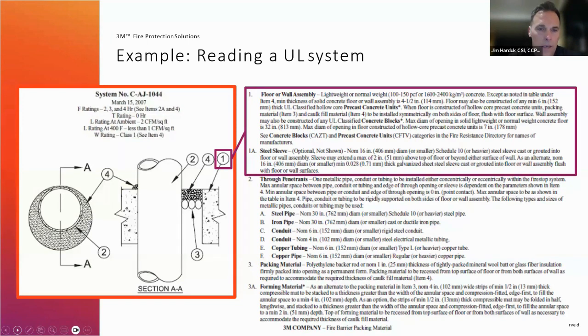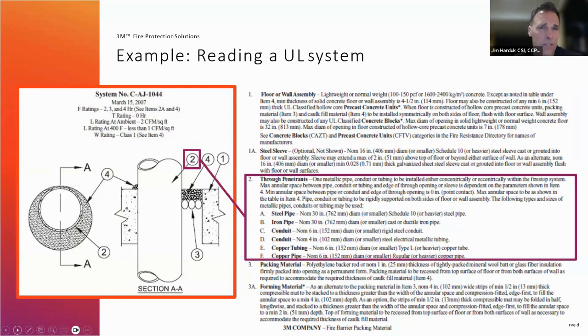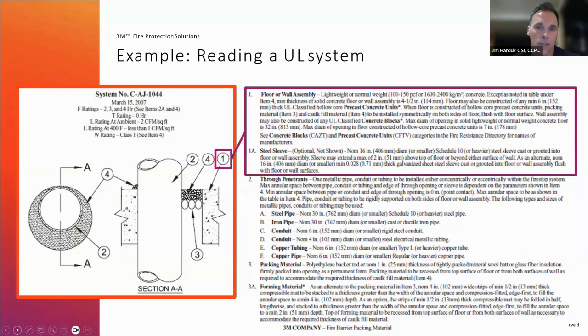And then in a system drawing, you have those items that I've just identified, and then you always have a small detail, and it'll show what the penetrating item is. It'll have a brief cutaway section of the floor or wall assembly, and it'll show a little bit about the fire stopping materials that are used. But they're always laid out the same way. So at the beginning of the system drawing, you have the identification of the assembly. It'll tell you if it's a floor or wall assembly. It'll tell you how it's constructed, what the thickness is. Sometimes sleeves are optional, sometimes they're required, and that will be clearly indicated in the text. And then it'll identify what the penetrating items are. So you'll see in paragraph number 2, it identifies what the through penetrants are.